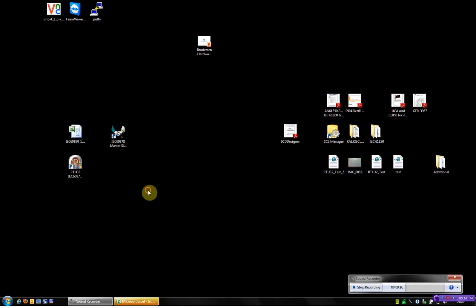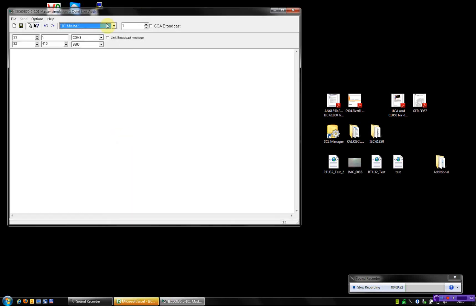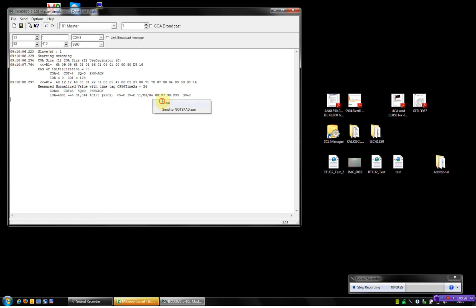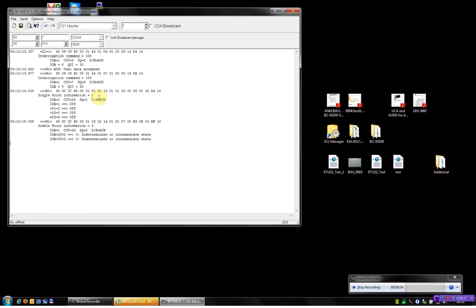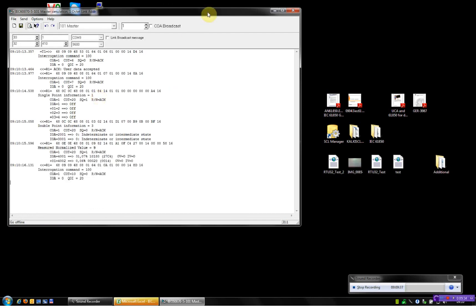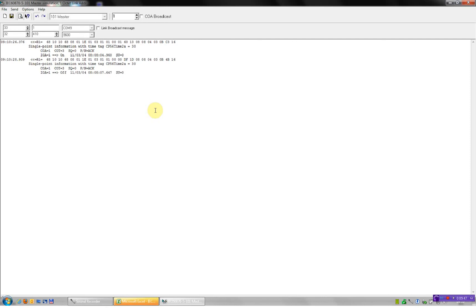I'll add a 101 master program to test if it's working. Here I connect to the 101 master. I'll send a general interrogation. We have our values. Then I'll try changing some of the digital inputs on the RTU32. We get an event, and off again. Then I'll try changing the analog inputs. Now let's wait — got a response.